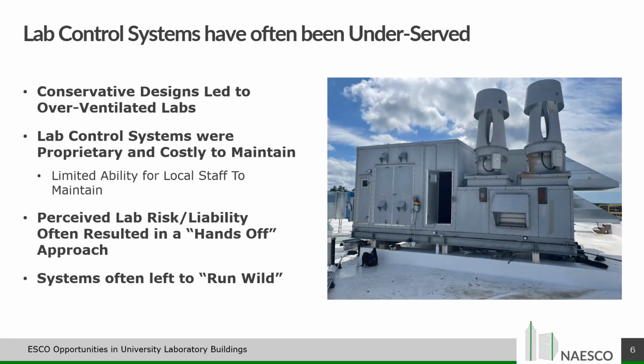This picture over to the right, this is a university in Massachusetts. This is a 100% outdoor air makeup air unit. You can see we've got the exhaust fans built right into the unit, and they have variable air volume capabilities. This is a fresh air bleed damper here. A VFD was supplied on the air handling unit, but they never set this up to operate properly. They had all the equipment to do it, but this lab, this number of labs, has been running as a constant air volume lab, running full out for years and years and years.